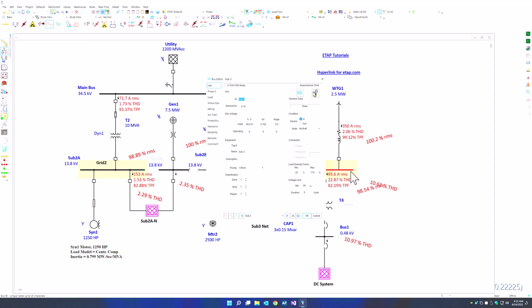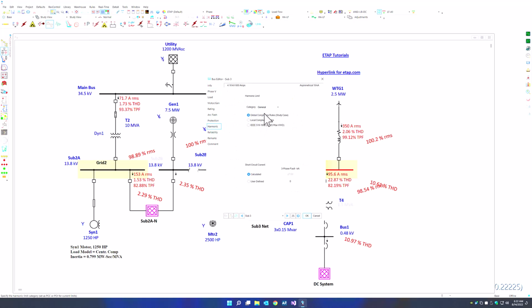You can also change the rules for harmonic emission limits by going into the harmonic page, and instead of using the global compliance rules, you can also use the local compliance rules. And these rules are based on ANSI 519 and the new AS-NZS 61000 or ENA G55, which is the British Harmonic Compatibility Limits. And of course, you have the IEC 61000 as well. So you can pick from these different emission rules and use those within the program such that we can essentially get an assessment of the harmonic limits that are being generated in the system and compare them versus these rules.